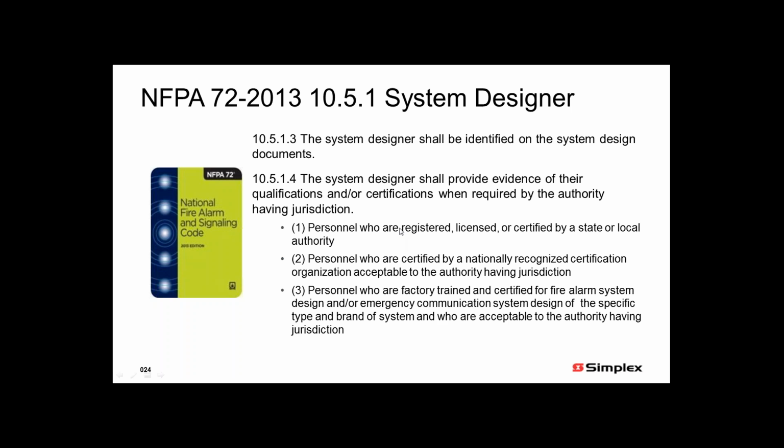Number two, a person who is certified by a nationally recognized certification organization. There are several of those throughout the globe that do a series of testing and then can issue certificates to people in recognition of their skills. And then we have another one here that, for example, Simplex, Tyco could help to supply personnel who are factory trained and certified for the fire alarm system design and/or emergency communication of the specific brand and type.